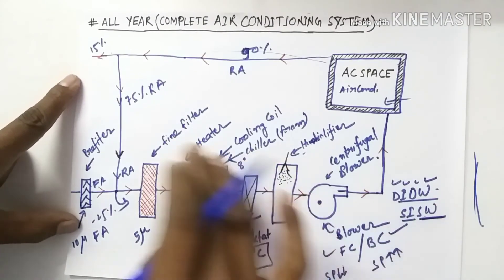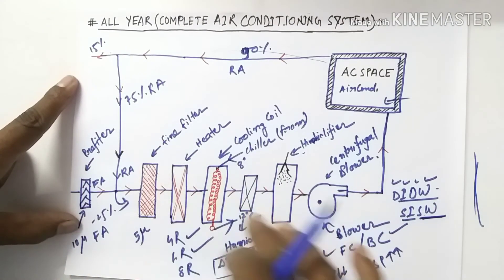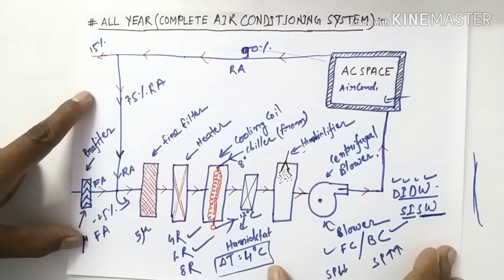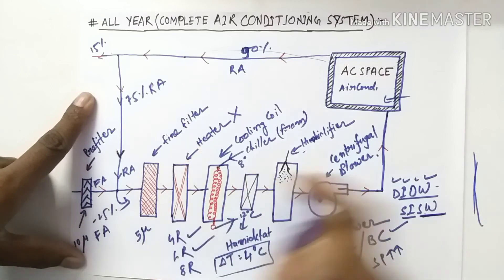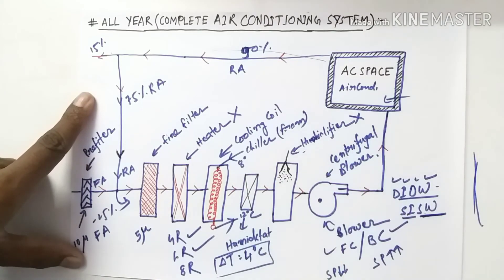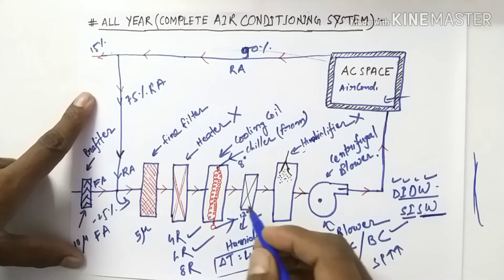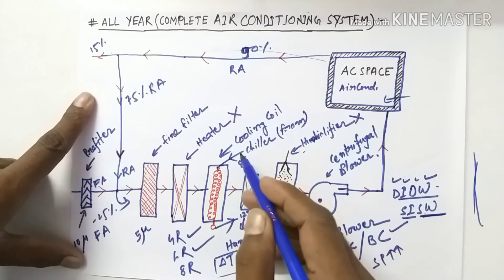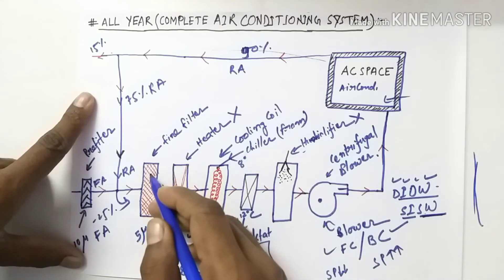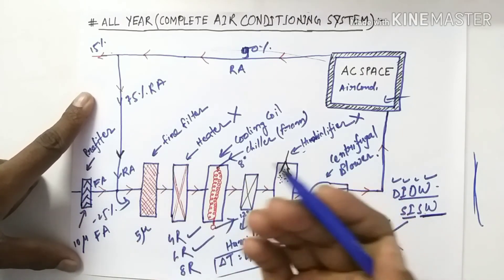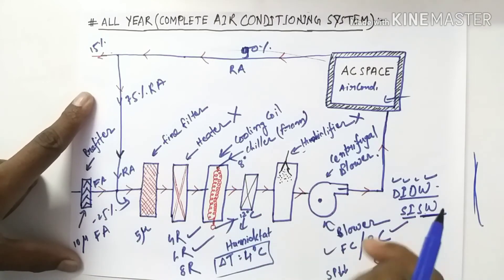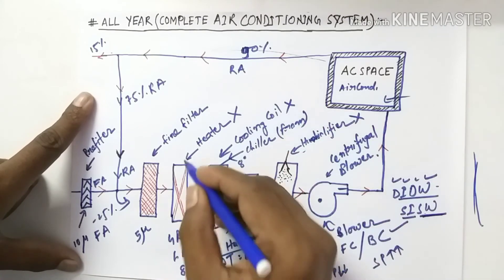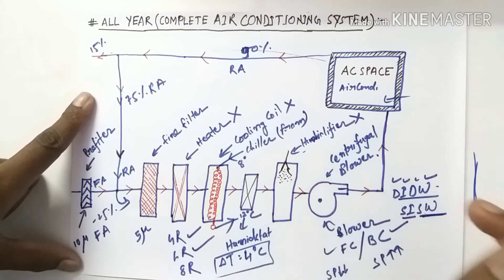If we are using this air conditioning system in summer conditions, then we have to shut off the heater and the humidifier. The blower will be on, the humidistat will be on, and the cooling coil will be on. The pre-filter and fine filter are always available. If we use this in winter conditions, then the cooling coil will be off and the heater will be on, and the humidifier will be on.